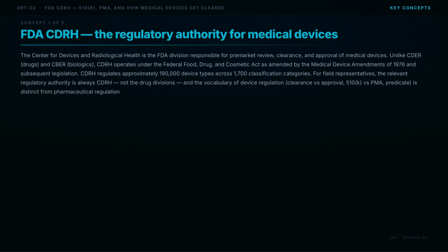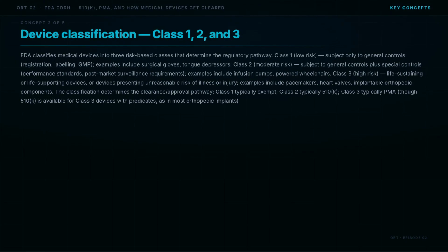The vocabulary of device regulation (clearance versus approval, 510K versus PMA, predicate) is distinct from pharmaceutical regulation. Device classification: Class I, II, and III. FDA classifies medical devices into 3 risk-based classes that determine the regulatory pathway. Class I, low risk, subject only to general controls: registration, labeling, GMP. Examples include surgical gloves, tongue depressors. Class II, moderate risk, subject to general controls plus special controls: performance standards, post-market surveillance requirements. Examples include infusion pumps, powered wheelchairs.